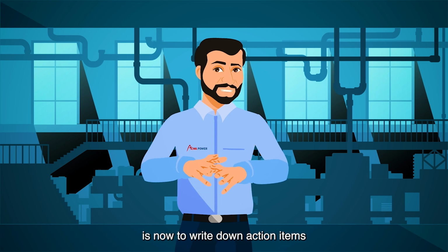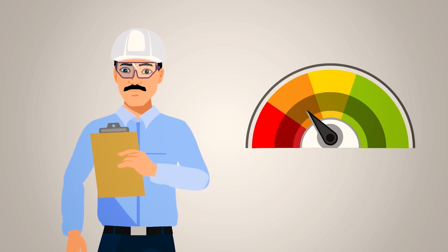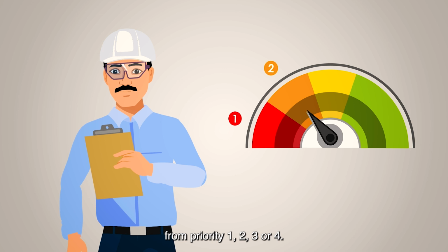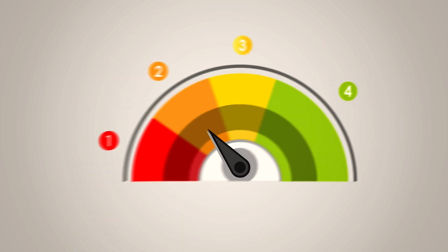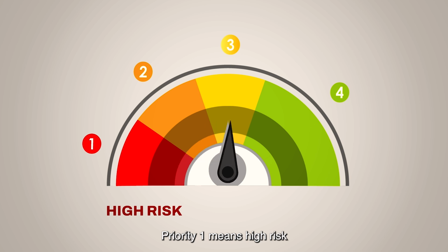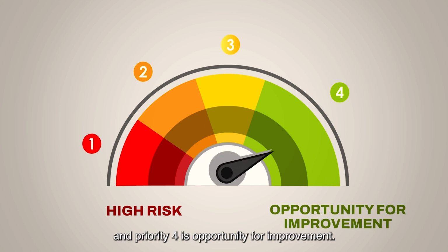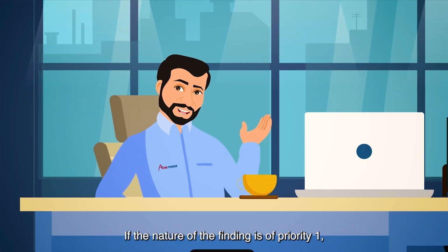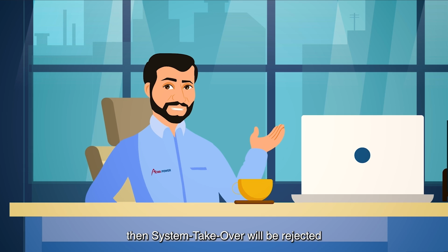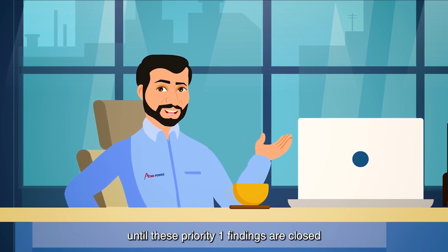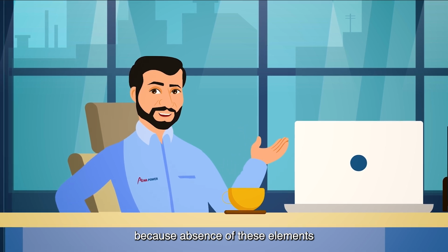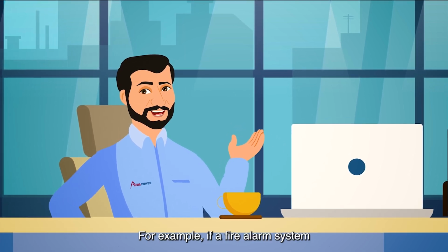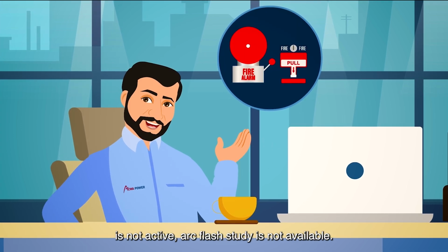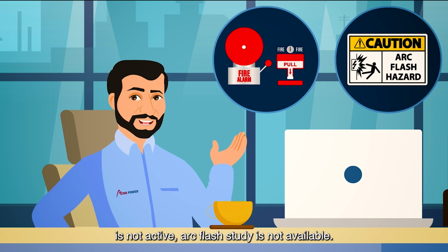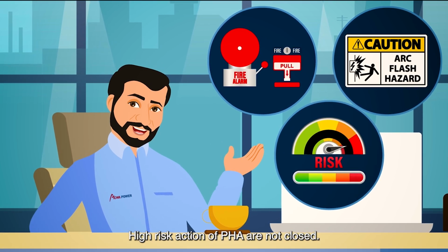The most important step is now to write down action items. While filling the PSSR checklist, the leader will allocate the findings a priority of 1, 2, 3, or 4. Priority 1 means high risk, and priority 4 is an opportunity for improvement. If the nature of the finding is priority 1, then system takeover will be rejected until these priority 1 findings are closed, because absence of these elements can cause serious incidents. For example, if the fire alarm system is not active, the arc flash study is not available, or high-risk actions of PHA are not closed.